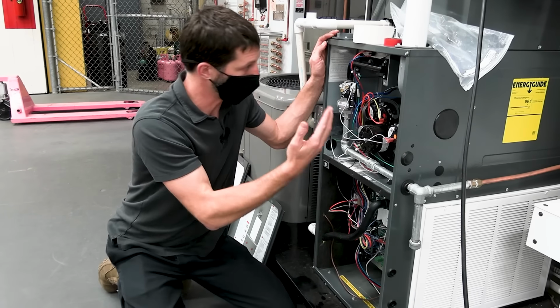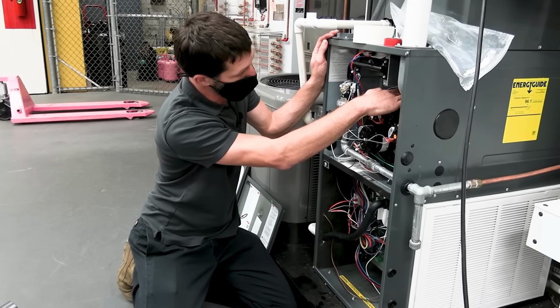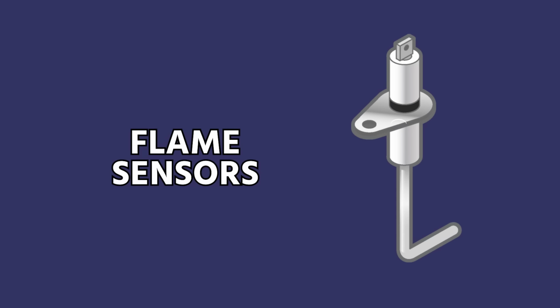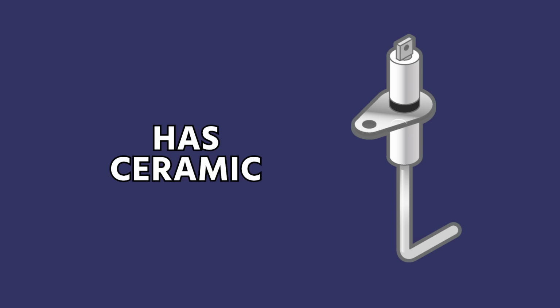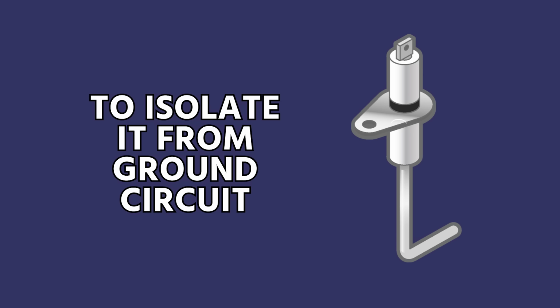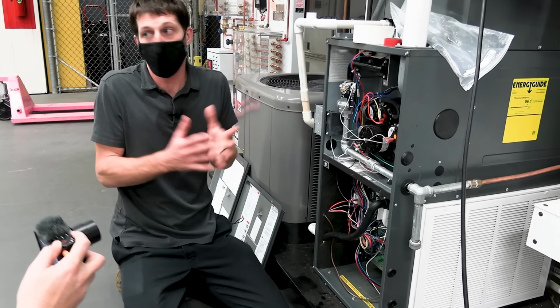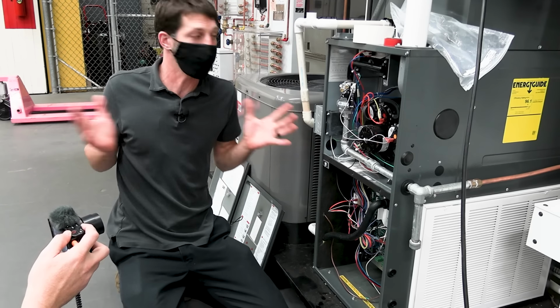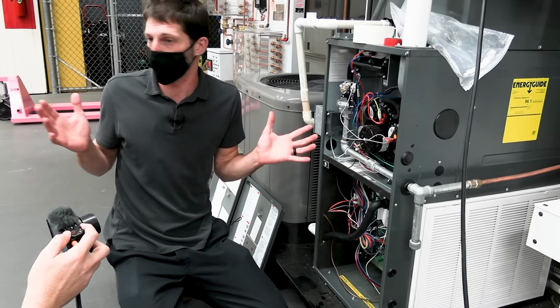There's rarely an instance where you need to change out that flame rod. It's also called a flame sensor. It doesn't sense anything. All it is is a stainless steel rod, and it has ceramic in order to isolate it from the ground circuit, because it doesn't want to touch the ground. That's all that is. There really is nothing to it. I can't believe how many flame rods are sold out there as flame sensors. It's crazy.